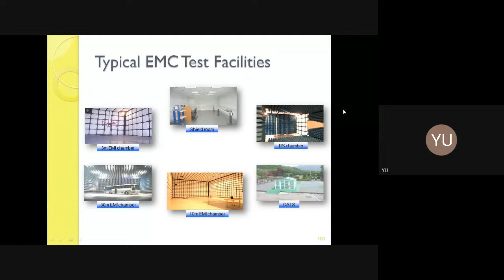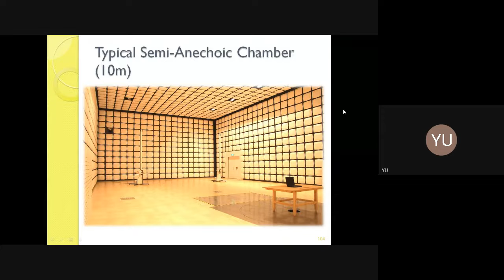This slide shows a typical anechoic chamber of 10 meters where the device can be placed inside, and the radiated emission or conducted emission can be measured outside the chamber. The simulation of the emission and radiation can be induced inside the chamber, and susceptibility can be checked to see how immune the system is and how it reacts in the presence of electromagnetic interference noise. That is the purpose of this test method.